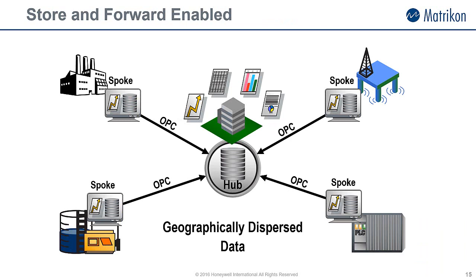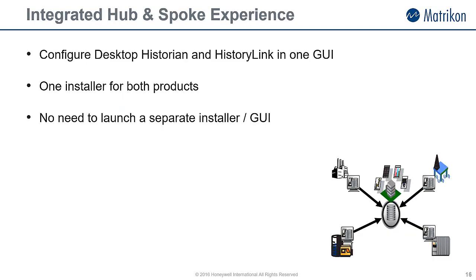Another great feature of the Matrikon OPC Desktop Historian is the built-in store and forward functionality, which is sometimes called hub and spoke. If you have multiple plants that are geographically dispersed, why not consider folding the data from Desktop Historian at your local plants back to a central location? Because of the open nature of OPC, your local sites can access the archived data locally, whilst enabling your head office to also access the data. This was possible in the past using Matrikon OPC Desktop Historian and HistoryLink. In the new version, Matrikon makes it easier to install and configure this system. When you install Matrikon Desktop Historian, you are given the option of a standalone or hub and spoke installation. If you choose hub and spoke, Matrikon HistoryLink is also installed, and both products are integrated into the same GUI for ease of use.